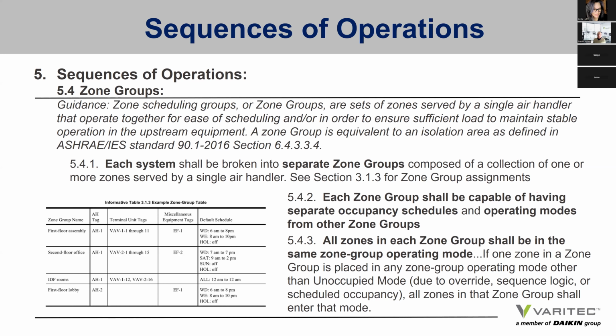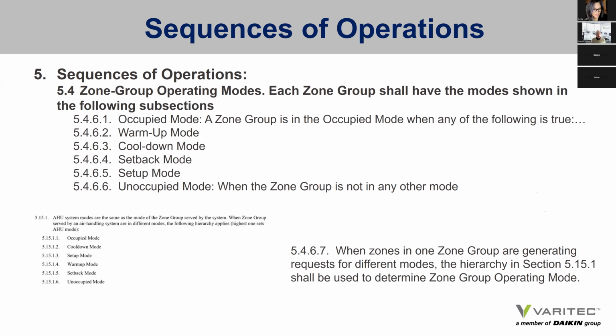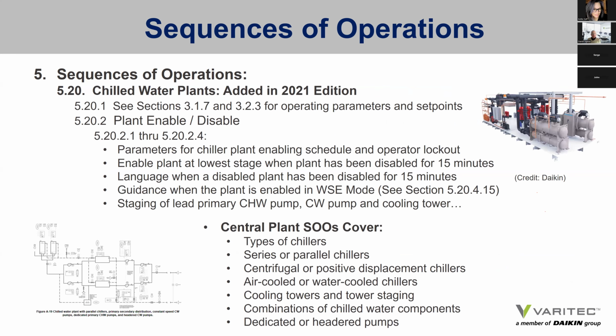All zones in each zone group shall be in the same zone group operating mode when it is in a given mode, and each zone group shall be capable of having separate occupancy schedules and operating modes from other zone groups. So the modes of operation will be occupied, warm-up, cool-down, setback. Some are scheduled, some are assigned per the zone. And then it gives, when zones in one zone group are generating requests for different modes, a hierarchy of what is to be assumed authority of the various zones. There's language on chilled water plants added in the 2021 edition. The plant sequences of operation assign plant enable and disable language.